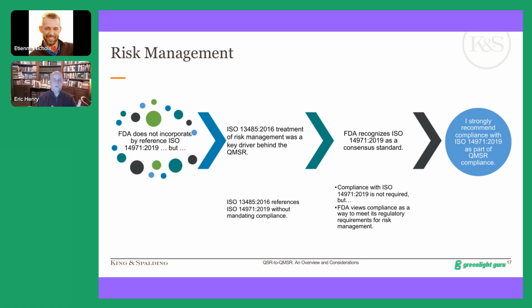It provides a clear, standardized way of walking through risk management, and through its 24971 guidance gives specific example tables for things like probability—breaking it into P1, the probability that a hazardous situation occurs, and P2, the probability that if it occurs it will cause harm—combining those and comparing to severity to come up with a risk rating. It also addresses data security. All those things are in the standard. It's well structured.